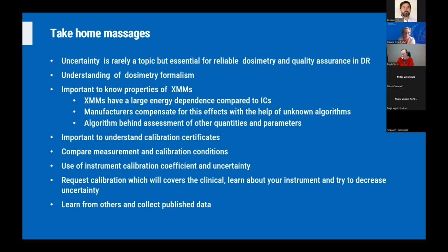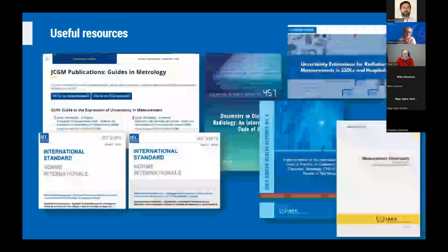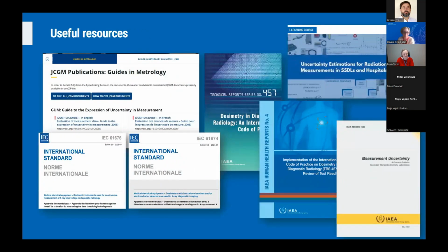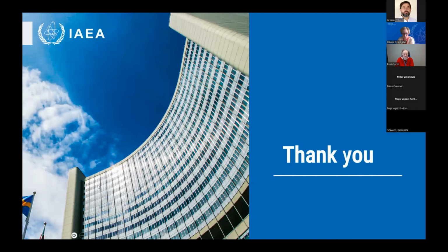In order to compensate or correct for energy dependence and different radiation qualities, it's always good to request calibration that covers the entire range of clinical use, because this could be one of the ways to decrease uncertainty of the measurements, and of course to use available resources and learn from others and from the published data. And on the final slide you can see a collection of good resources for starting creating an uncertainty budget in the clinical measurements in diagnostic radiology. With this, I would like to thank you for your attention.